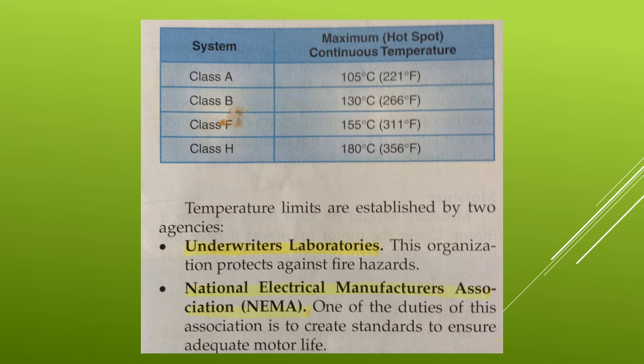Temperature limits are established by two agencies, the Underwriters Laboratories, as you can see on the screen. This organization protects against fire hazards. The other is the National Electrical Manufacturers Association, or NEMA. One of the duties of this association is to create standards to ensure adequate motor life. The nameplate data generally gives the allowable or maximum temperature rise above the ambient air for motor operation. If these are observed, the hotspot temperature of the motor should remain within the specified value for the insulation system used. The normal maximum ambient temperature is 40 degrees centigrade or 104 degrees Fahrenheit for most motor ratings.